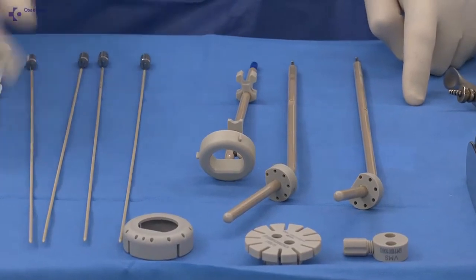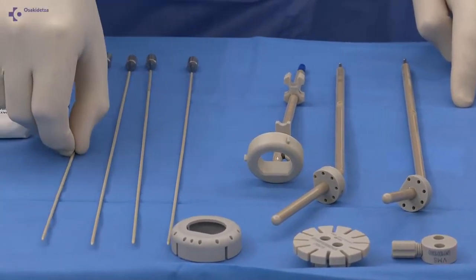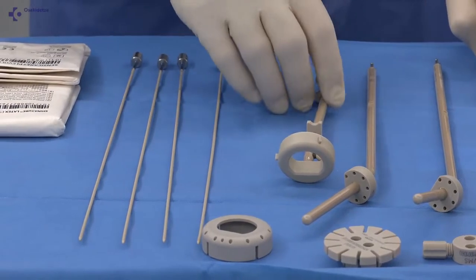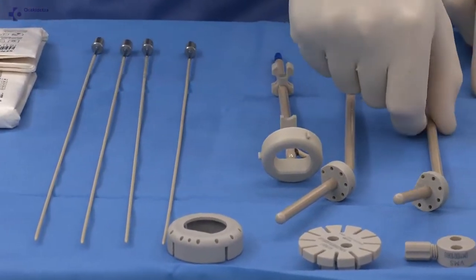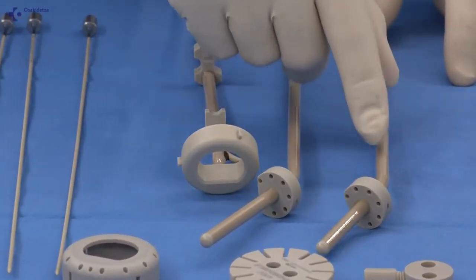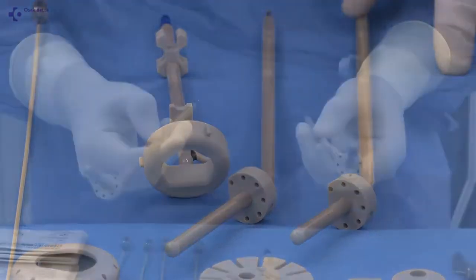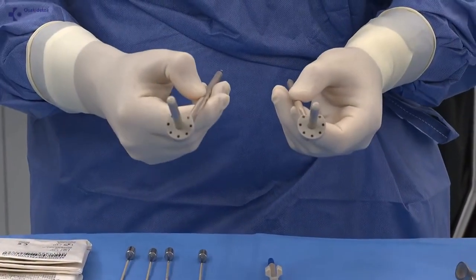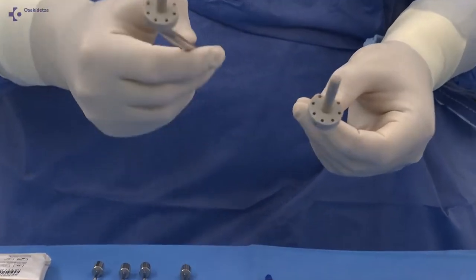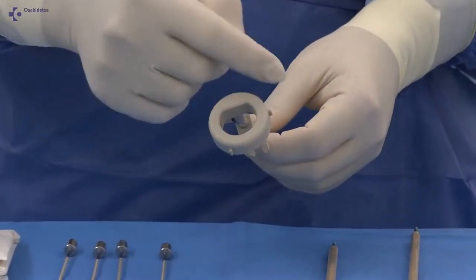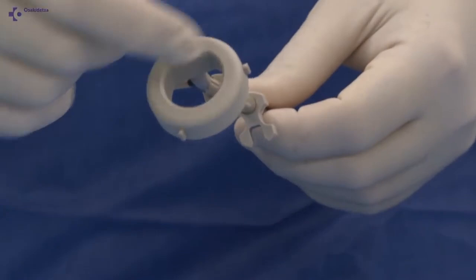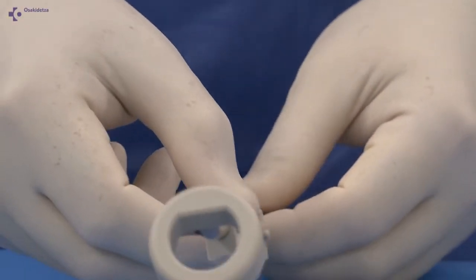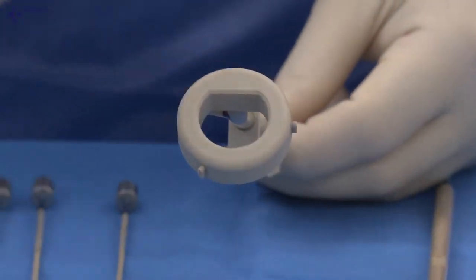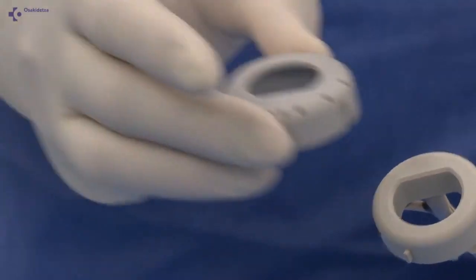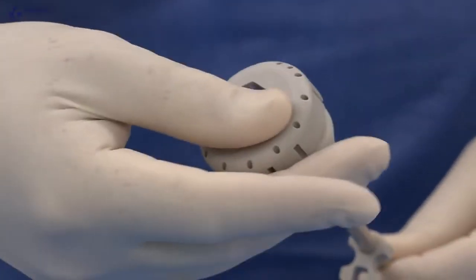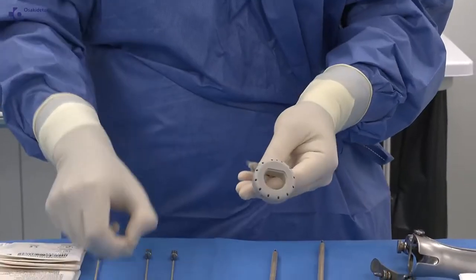Additionally, for this procedure, we use applicators made of paramagnetic materials compatible with MRI for positioning the radioactive source. Of the various types on the market, we have opted for a Vienna applicator, which offers several sizes and curvatures of intrauterine probes, as well as a ring-shaped probe, allowing a good fit to the anatomy of each patient. Moreover, this applicator comes with a device through which plastic needles can be inserted, allowing delivery of additional radiation to the parametria.